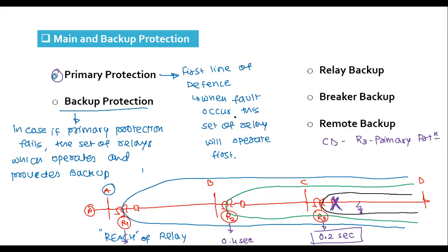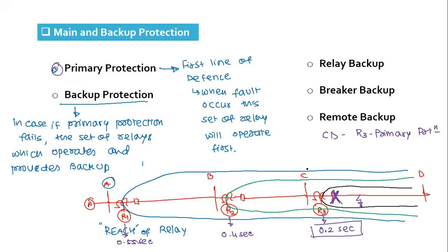If this relay does not operate and does not trip the breaker here, the fault is not cleared, and the generator is still feeding the fault. So the next choice to disconnect the fault is to open this breaker. R2 will operate after some time delay and trip the breaker over here.